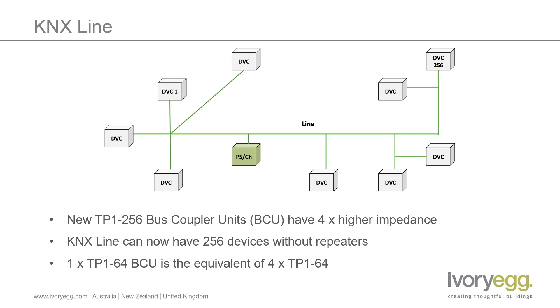If you have a larger number of the older devices in the system, you can always use the line repeater in the way that we are used to. The other design limitations remain: no loops, maximum of 350 meters from a device to a power supply, and no more than 1000 meters in a single line.